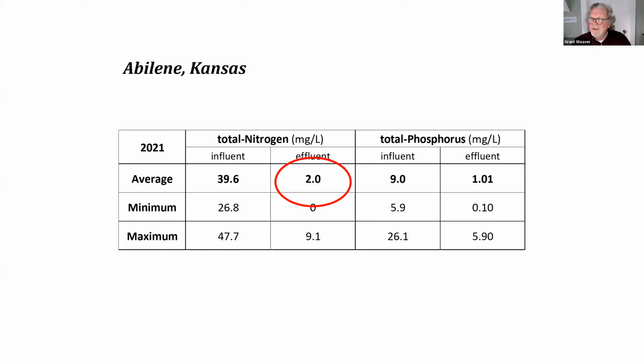So you can see there's no nitrates, all right? If there's no nitrates, there's no competition for the volatile fatty acids, the candy. When you have everything going on in one vessel, this is really key. And you don't see total nitrogen numbers that low very often. That's a really excellent number, and it's not because the influent is low, right? You can see the influent's almost 40.